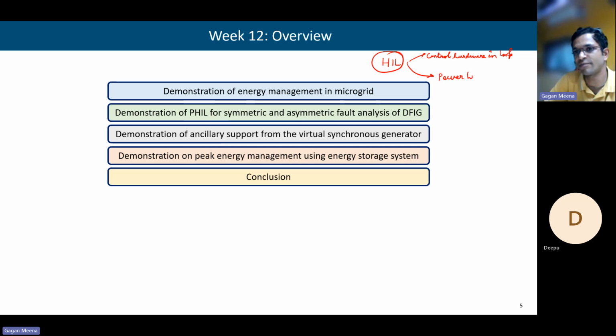The second type is power hardware in loop, where power is exchanged with the device under test, and these devices under test are power hardware. In control hardware in loop, devices work at smaller voltage levels, 5 or 10 volts, not more. But power hardware in loop involves power devices, for example synchronous generator, induction machine, DC motor, PV, or a battery operating at 220 volts. All these power devices need to be interfaced with the real-time digital simulator. However, the output of the simulator is only up to about plus minus 5 volts or 0 to 10 volts, while the power device requires higher voltage and current levels.